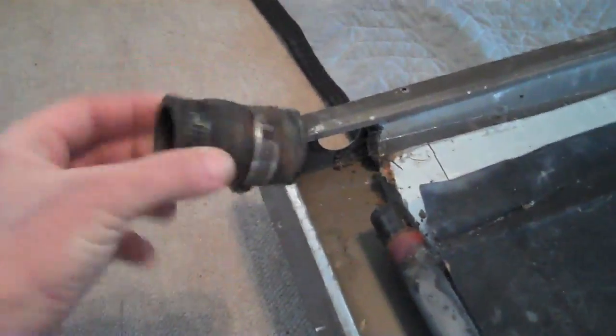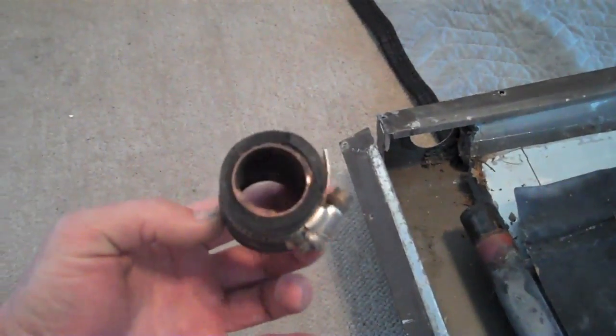We took the corners apart where the screws are. You can see the header pipe right here. On one end they basically had a piece of radiator hose with two hose clamps, and you would stick a screwdriver through here to tighten down the hose clamp connection — a very inexpensive way of making a coupler, although not necessarily the ideal way.